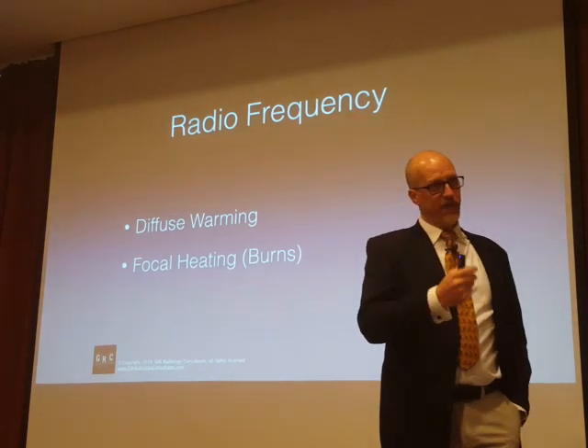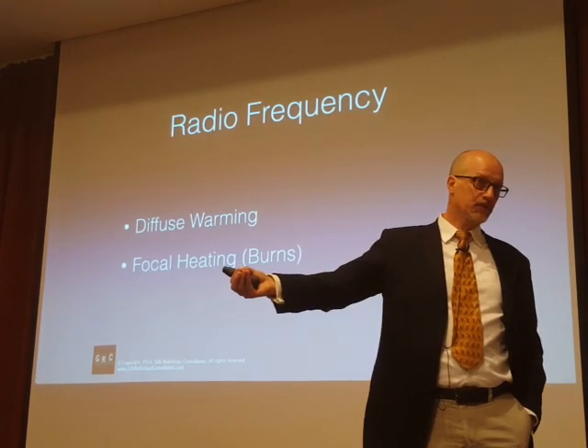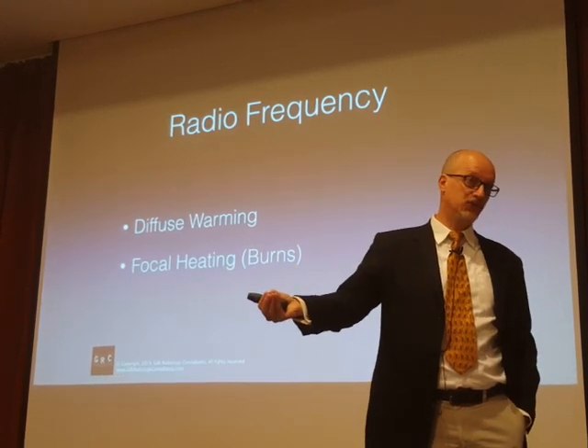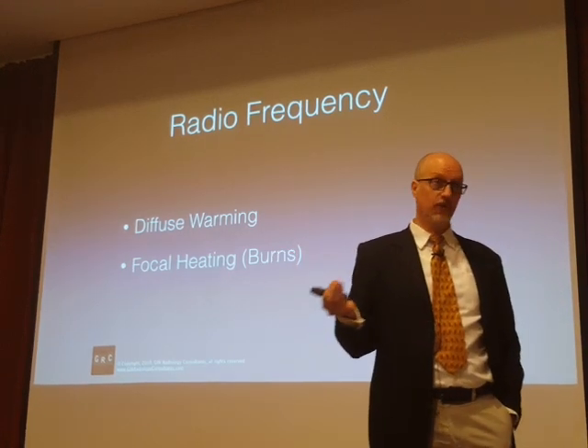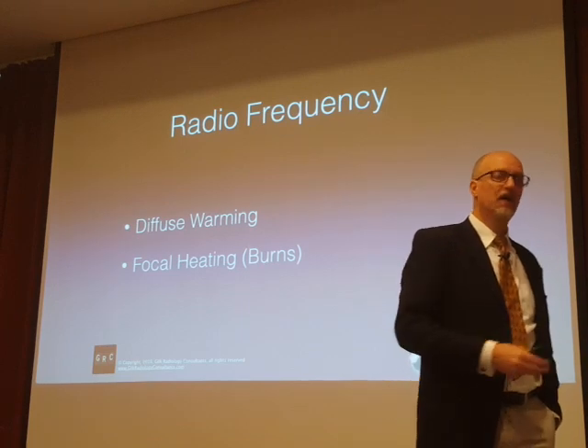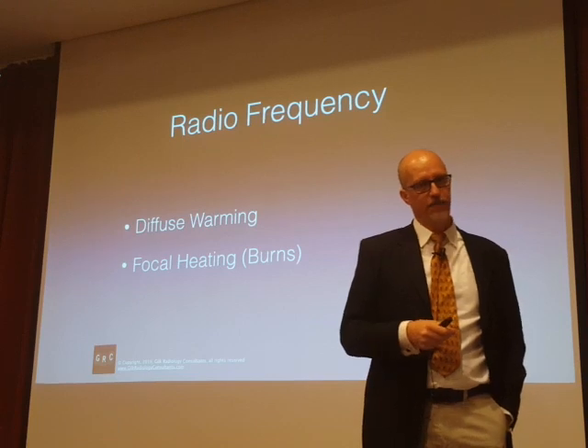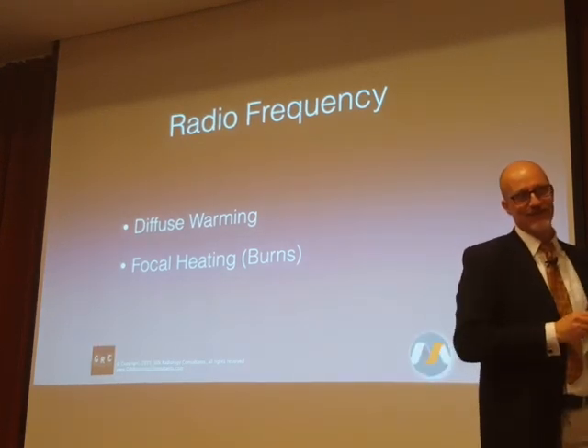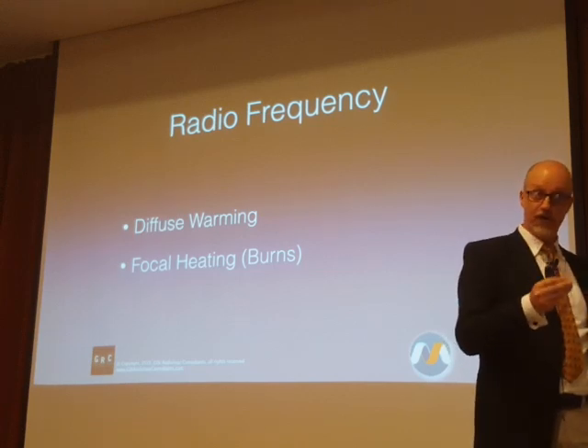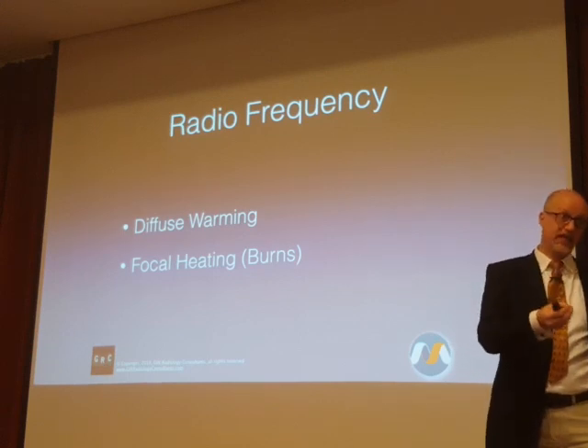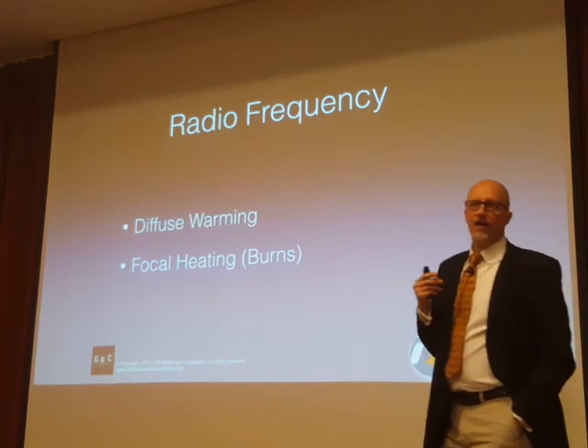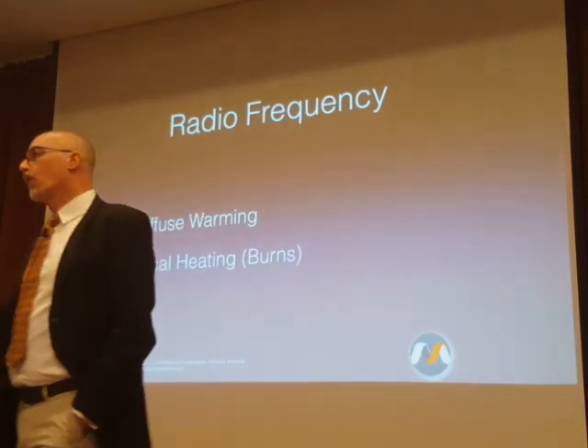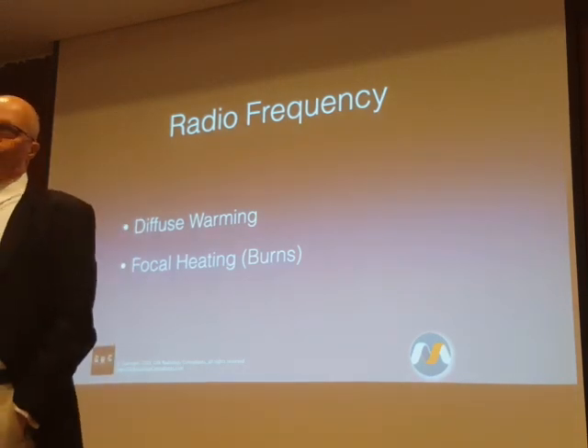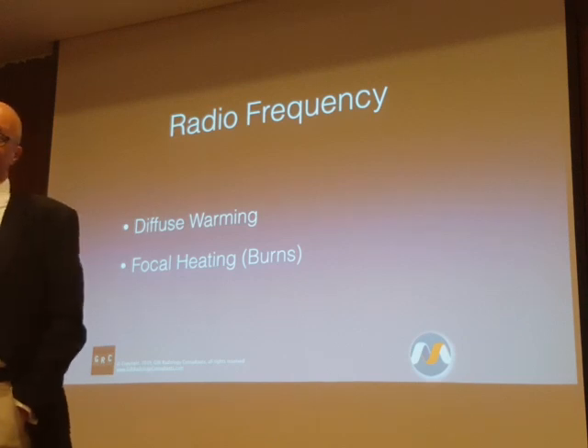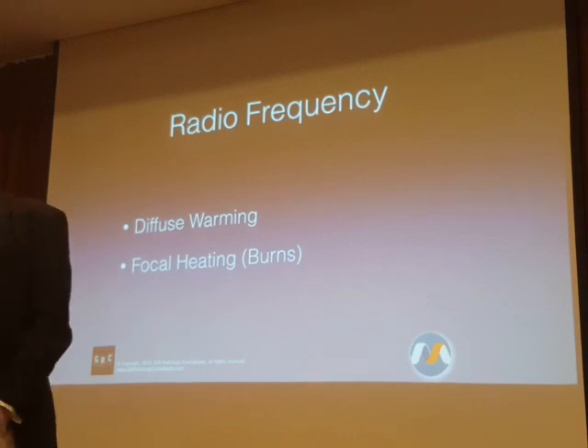For a number of those patients, we can follow the protocols that we would for an MR conditional pacemaker, with the monitoring and the supervision and device check. And those patients appear to have similar outcomes to many of the MR conditional ones. It's not true for all patients, and it's not true for all devices. That's a more complicated question to answer than we have time for right now, but I would direct you to the publication from the Heart Rhythm Society for a much more in-depth response. While it is possible to produce some warming from time-varying gradients, the risk of warming or heating associated with time-varying gradients is actually pretty tiny. If we're talking about heating, 99% of the time we're talking about radio frequency.